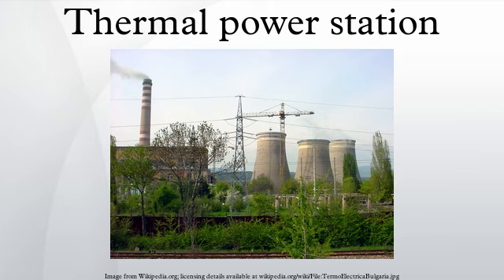Superheater. Fossil fuel power plants often have a superheater section in the steam generating furnace. The steam passes through drying equipment inside the steam drum onto the superheater, a set of tubes in the furnace. Here the steam picks up more energy from hot flue gases outside the tubing and its temperature is now superheated above the saturation temperature. The superheated steam is then piped through the main steam lines to the valves before the high-pressure turbine. Nuclear-powered steam plants do not have such sections but produce steam at essentially saturated conditions. Experimental nuclear plants were equipped with fossil-fired superheaters in an attempt to improve overall plant operating cost.